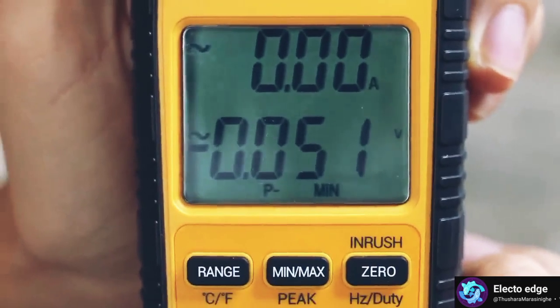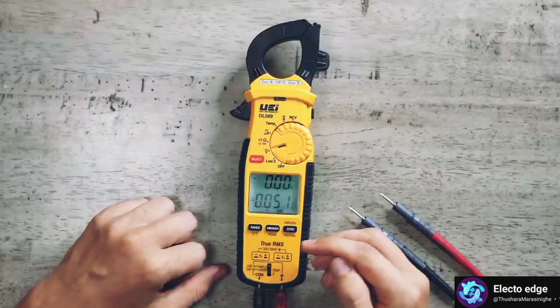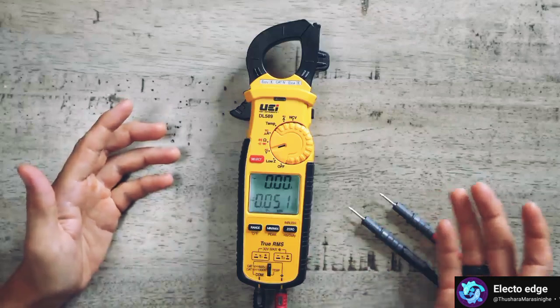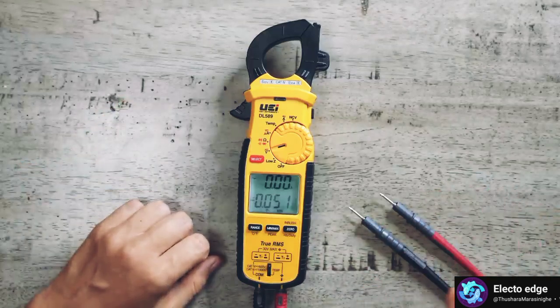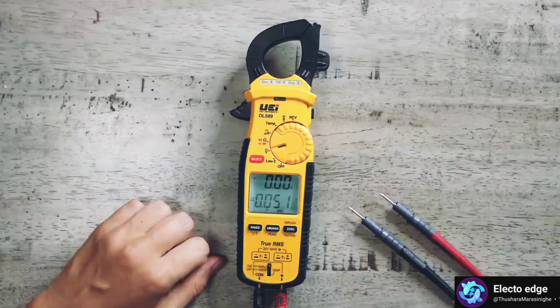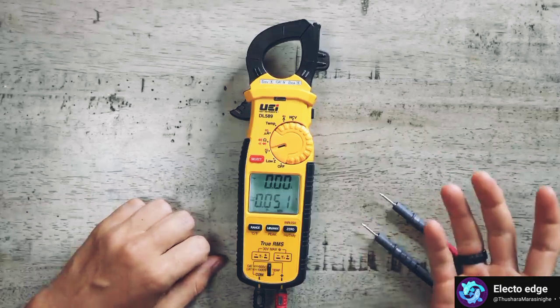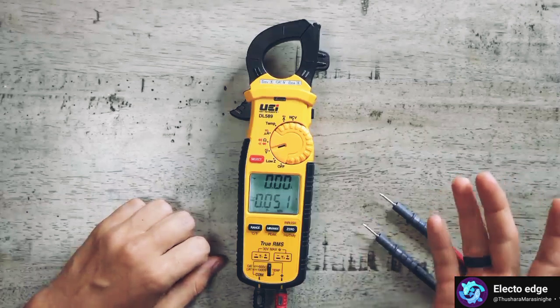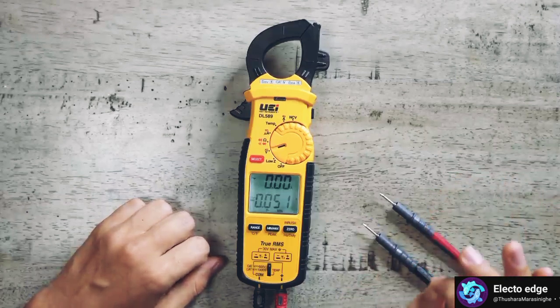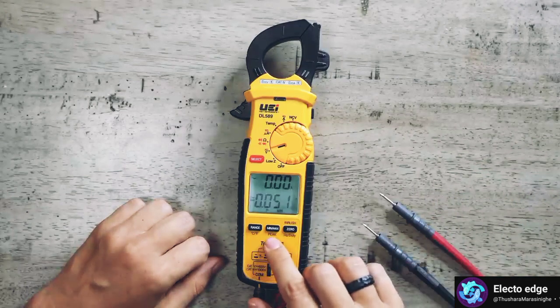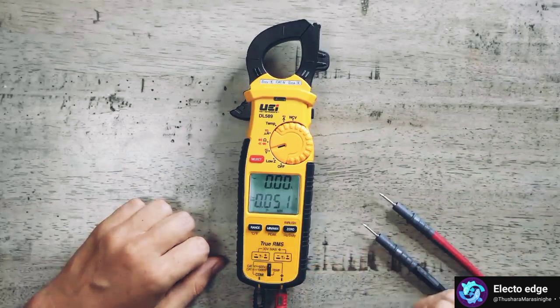we have peak max and peak minimum. When you select peak, it's the same thing as the regular minimum and maximum, except it's almost 3 times as sensitive, so it reacts a lot faster. For example, if you're measuring voltage and it spikes just for a fraction of a second, if you have it set to peak max, it'll still be able to catch that.